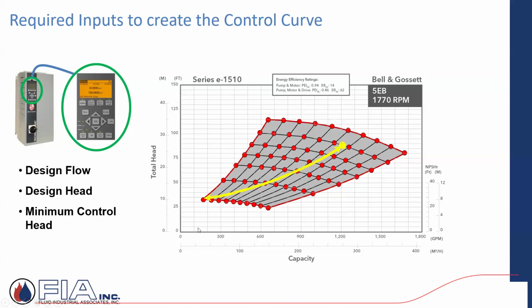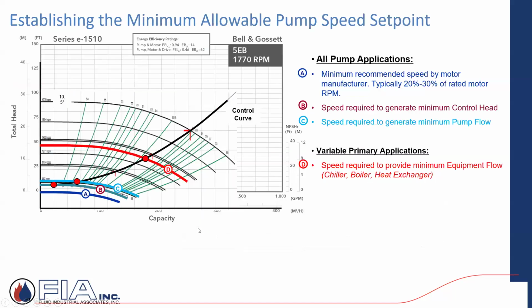Here's one of those, perhaps it might be a drive, and you're saying, hey, how do I establish that control curve as opposed to system curve? And all they're saying here is you have a couple different points. Minimum recommended speed by the motor manufacturer, typically 20, 30%. Maybe it's speed required to generate minimum control head, we just talked about. Maybe it's to generate minimum pump flow. Pump manufacturer says, hey, I got a range from maximum to minimum. I got to honor that minimum.